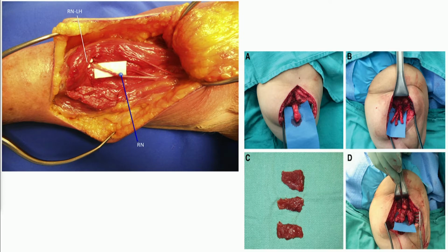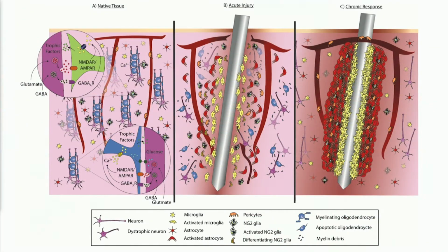The ideal solution would be an intraneural electrode with high resolution and fidelity, allowing for single neuron selectivity and two-way communication, combined with mitigation of foreign body reaction. Foreign body reaction has been compared to an ongoing wound healing response that remains unresolved due to the presence of foreign material that cannot be phagocytosed, and that leads to degradation and encapsulation of the implanted electrode, as well as damage to the surrounding tissue.